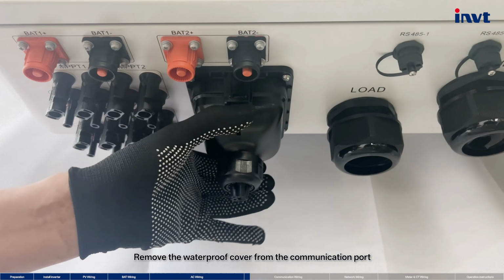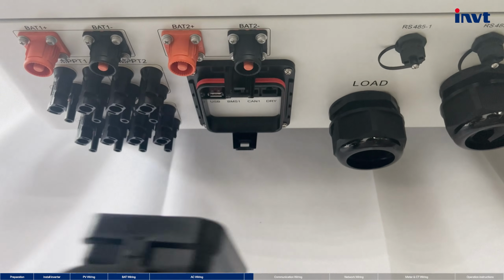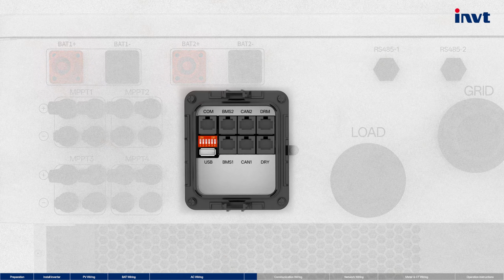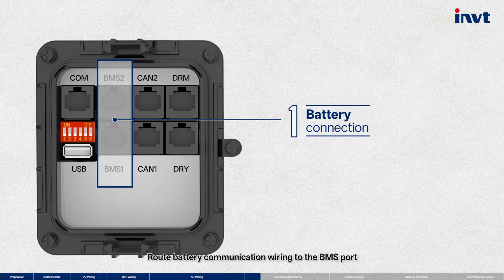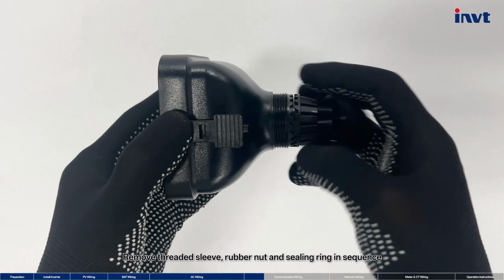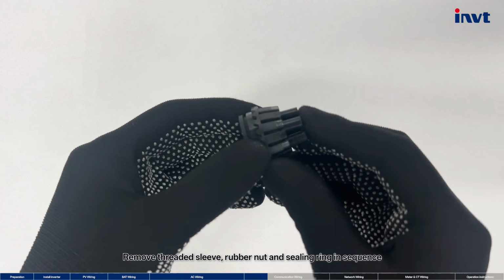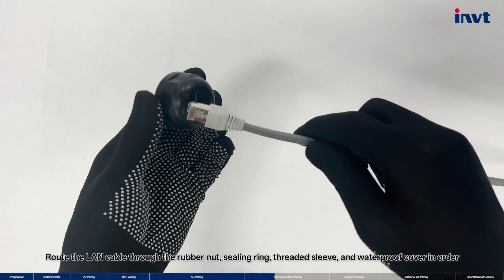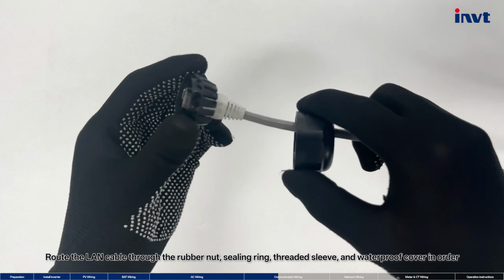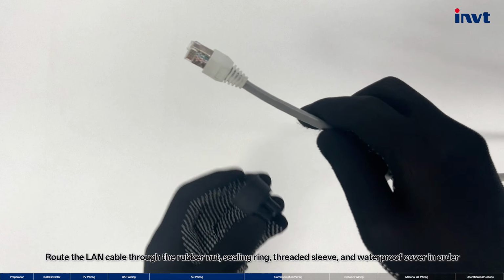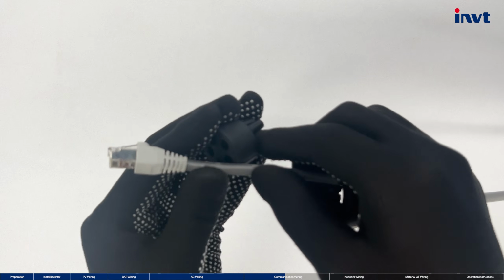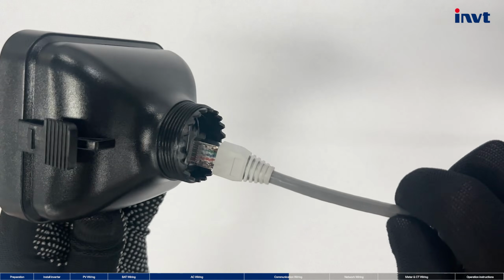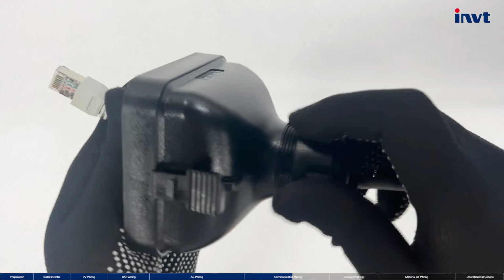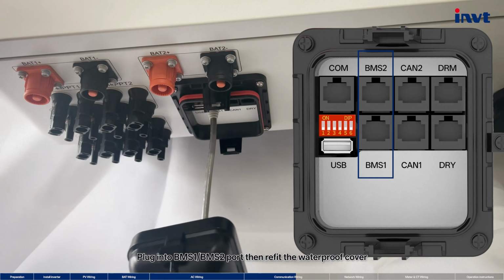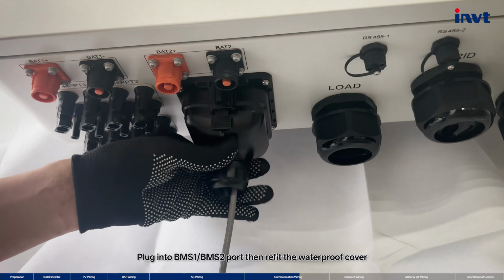Remove the waterproof cover from the communication port. Route battery communication wiring to the BMS port. Remove threaded sleeve, rubber nut, and sealing ring in sequence. Slit one cable gland entry for LAN cable routing. Route the LAN cable through the rubber nut, sealing ring, threaded sleeve, and waterproof cover in order. Plug into BMS 1 or BMS 2 port, then refit the waterproof cover.